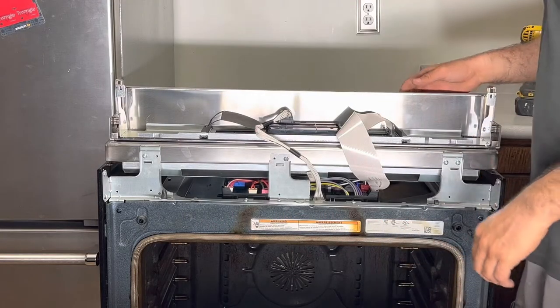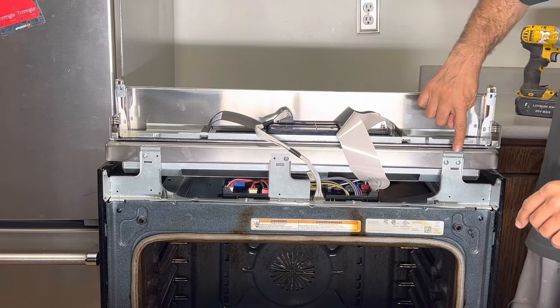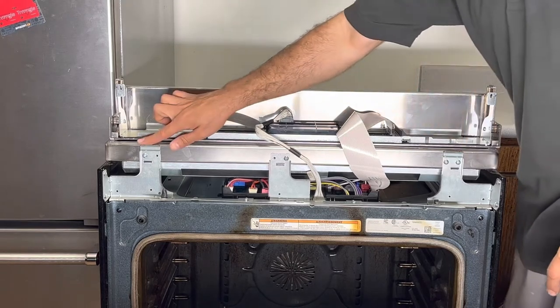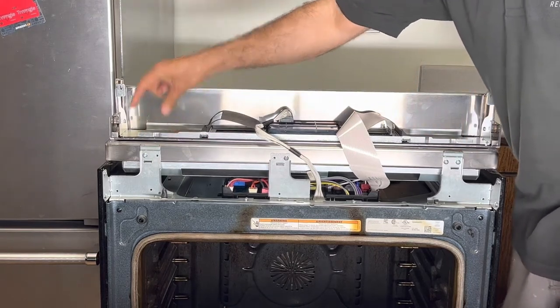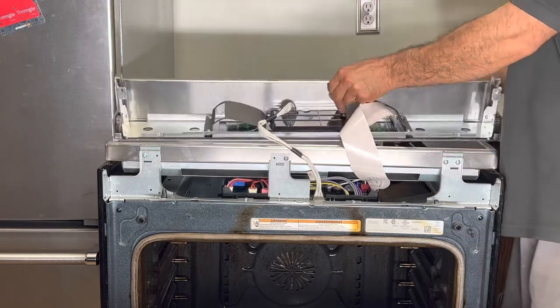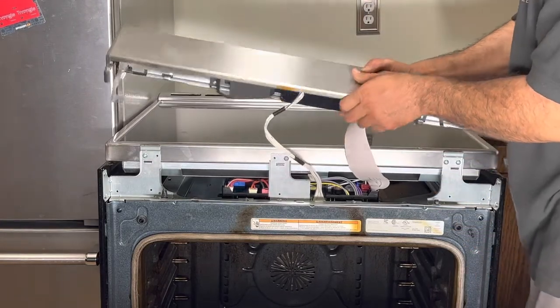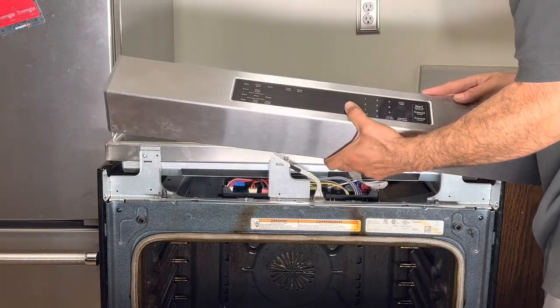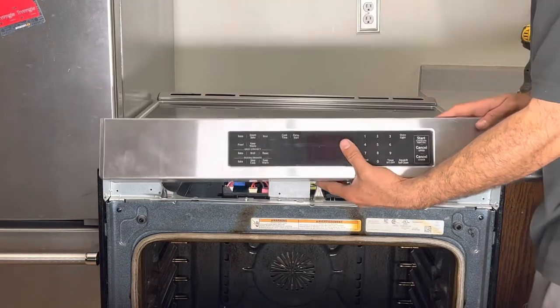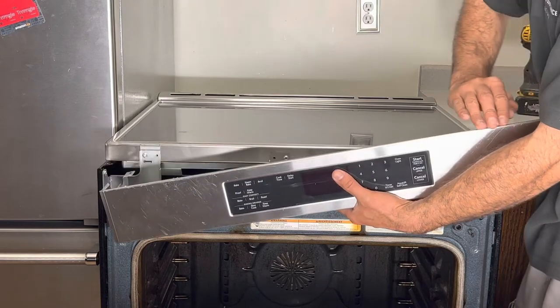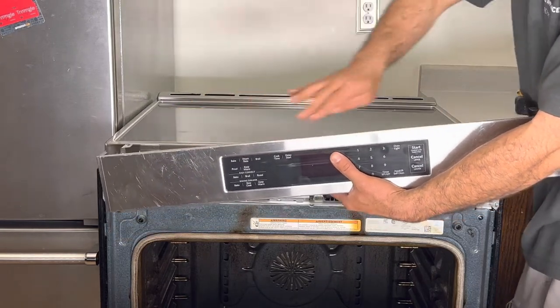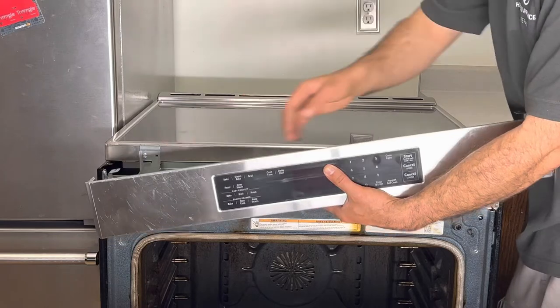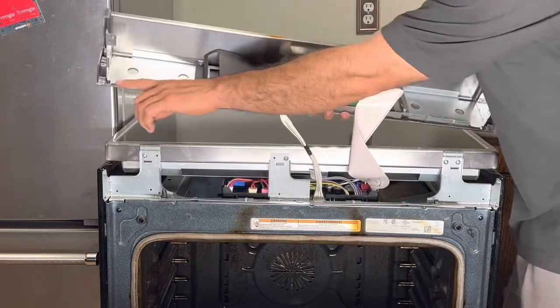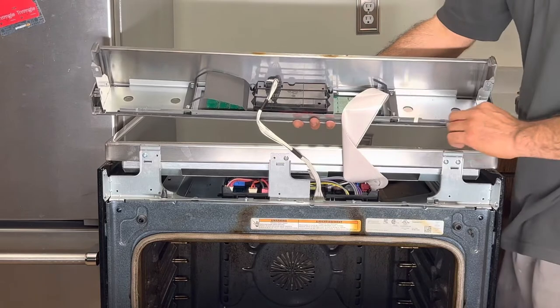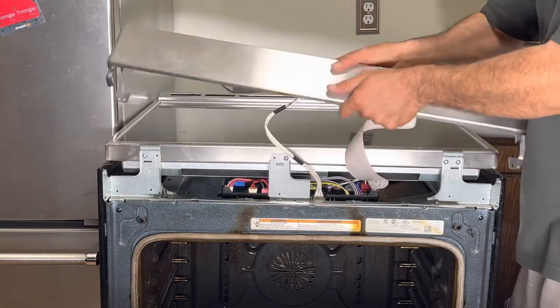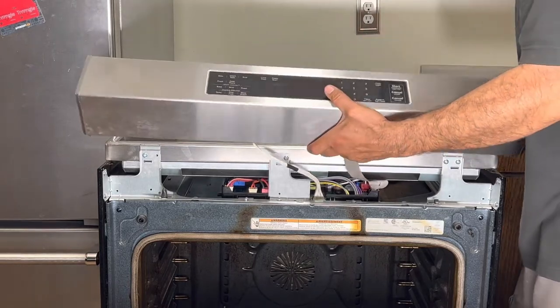When reinstalling the control board, you can see a slot here, another slot here, they go in this area. So I'll flip this back in. On this unit, I can see they do not have a good gasket insulation here. There's no gasket here, there's no gasket here. But at the back of the control panel there's a very tiny gasket, and I don't think that's really going to help. There's supposed to be a proper gasket installed from the factory.